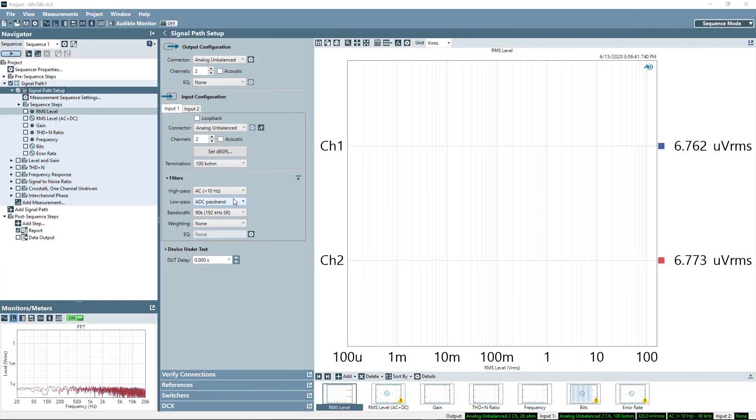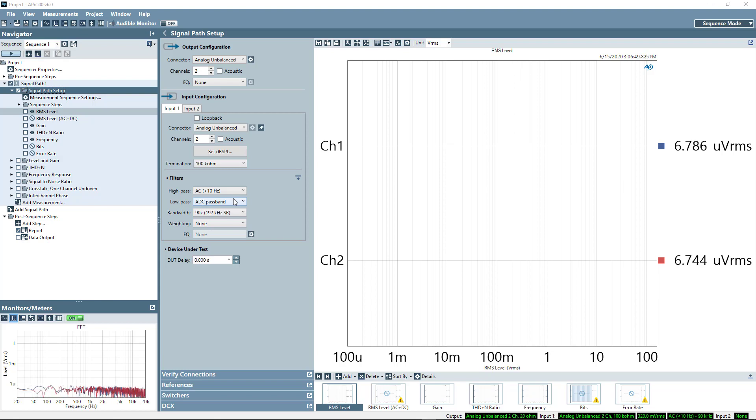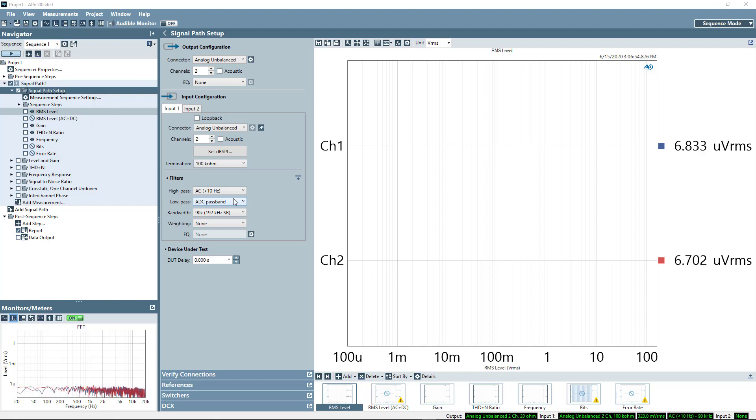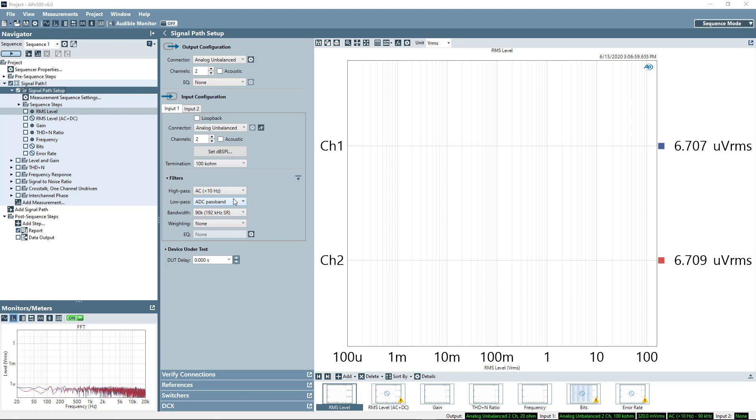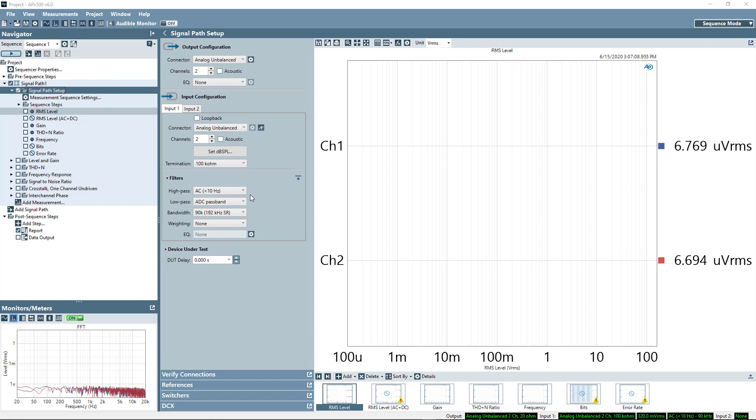Hello, and welcome to this audio test session with APX. In this test session, we'll be looking at testing a pair of MEMS microphones, but we'll be taking advantage of a new feature in APX500 version 6.0, multi-input, or the ability to have two different inputs, in this case an analog input and a digital input, active simultaneously.